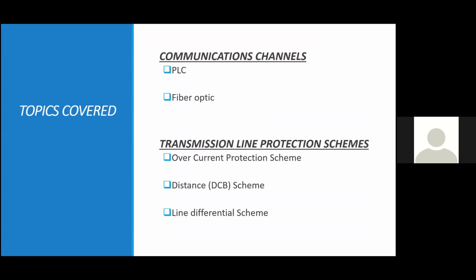If you want to protect a transmission line, you should take into consideration primarily two things. The first is, what kind of transmission line protection scheme are we going to use? Is it going to be an overcurrent protection scheme? Is it going to be a distance-based protection scheme, or a differential or current differential protection scheme? To implement all of these schemes, excluding the overcurrent protection scheme, for the remaining two schemes, you need a communication channel between the local end relay and the remote end relay.